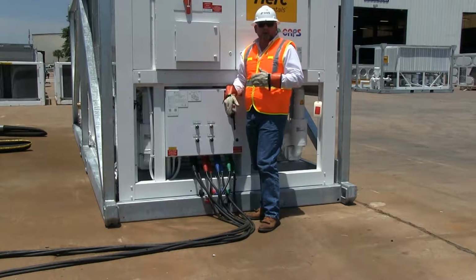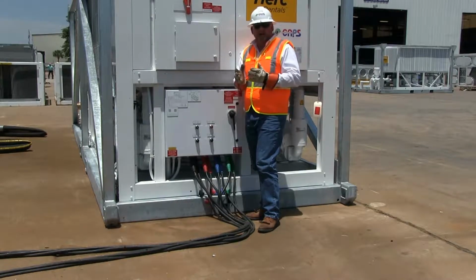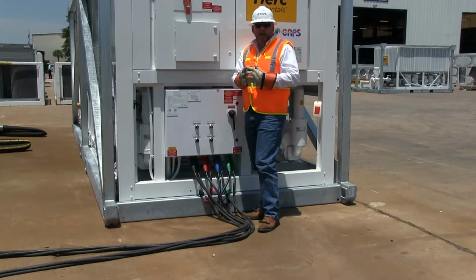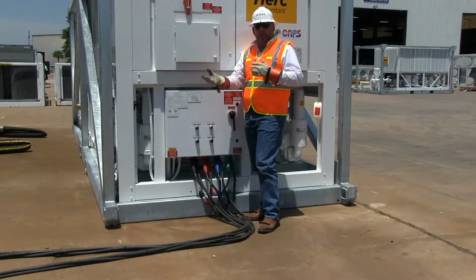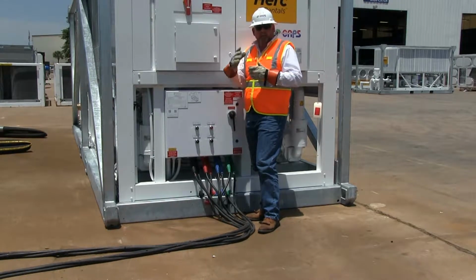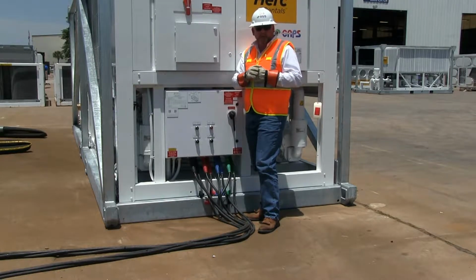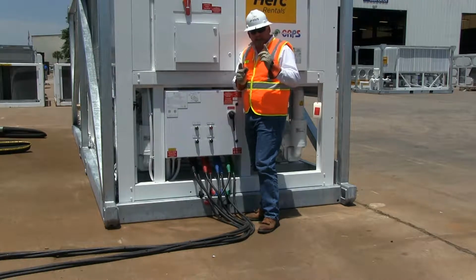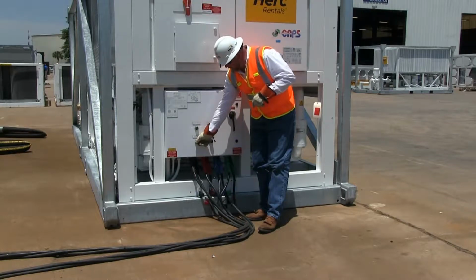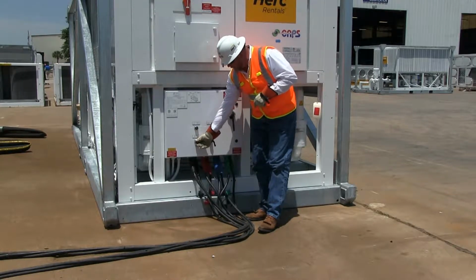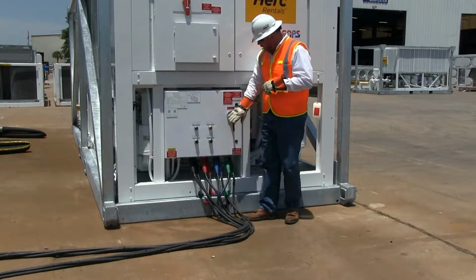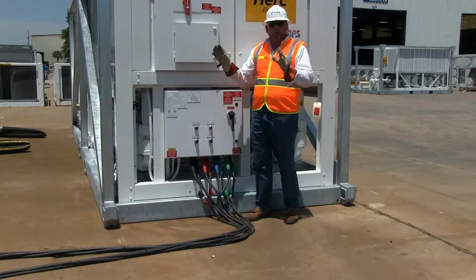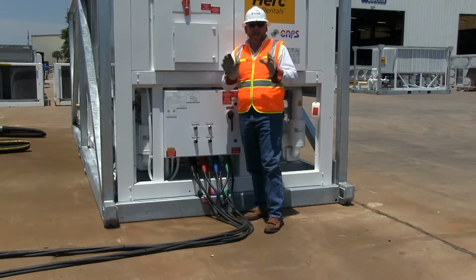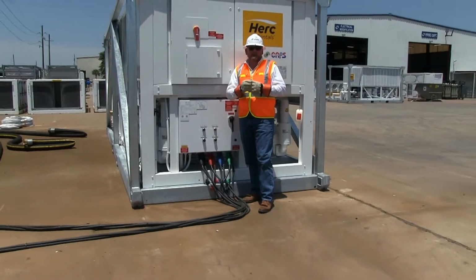We always hook the power up to the machine first so that we can start the timer and get past that 1 hour lapse portion until we do our plumbing and our air handler and the other parts of the job that are required for a particular application. In order to start that timer though, we'll have to go to the main system switch here and turn it on. Notice that our pump switch is off and our pump breaker is off. At this point, all we're doing is warming the compressor up while we're continuing with the rest of our setup.